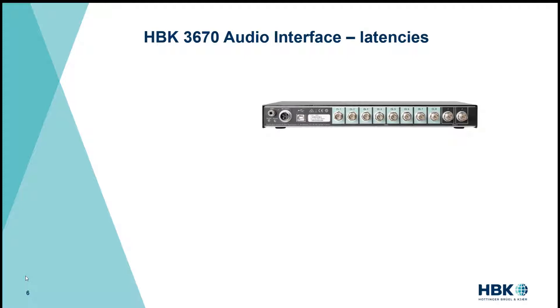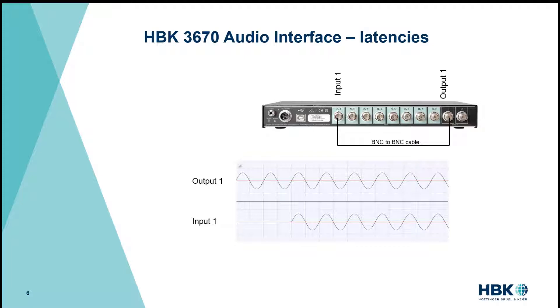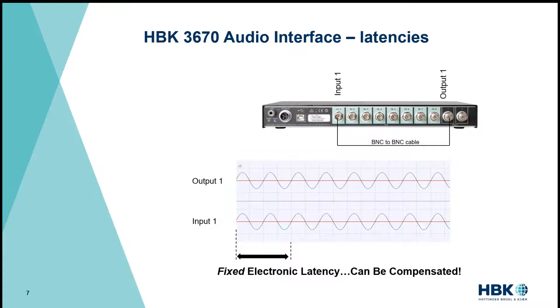Let me explain what we mean by latency. If you connect input one to output one of the 3670 with a BNC to BNC cable and generate a sine wave, you will notice a time delay between the two. This is called the electronic latency. It is not due to cable length but rather due to the firmware and driver processing time. The 3670 belongs to a class of electroacoustic interfaces that have fixed electronic latency, so for each measurement we know the exact number of digital samples between the input and the output and can compensate for it once data is captured.